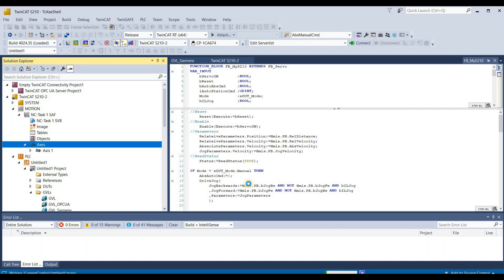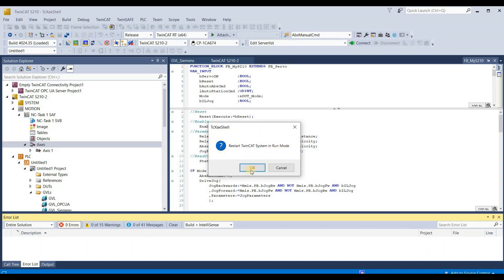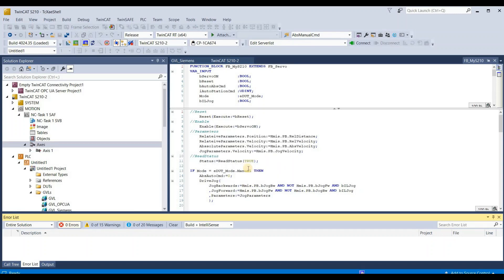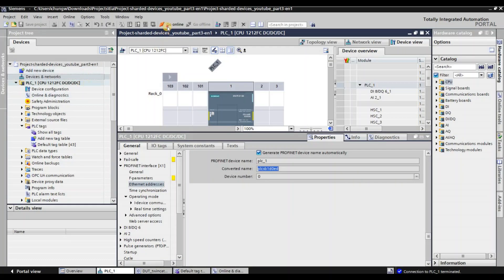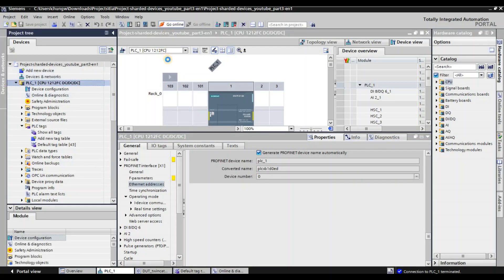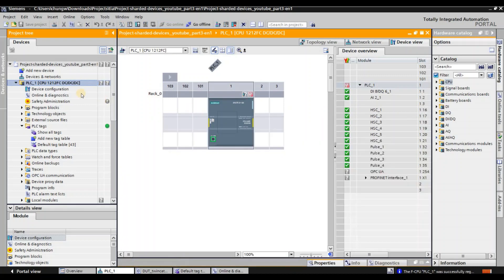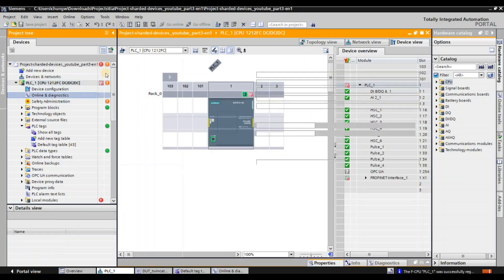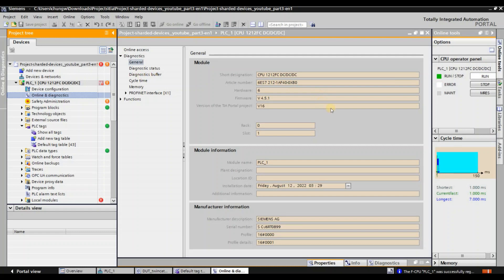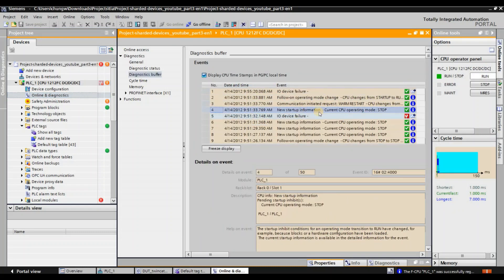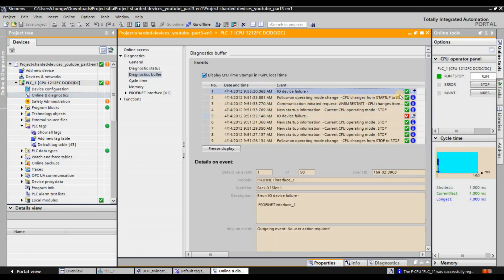Save it and download the project to the device. It will take a second or two. When asked if you want to reset your system in run mode, choose Yes. Now let me go to the S7 1200 side. Go to Online and go to Online Diagnostics, then Diagnostics Buffers. See if there's an error called 'IO device failure.' Now the error is fixed — there's no error here.